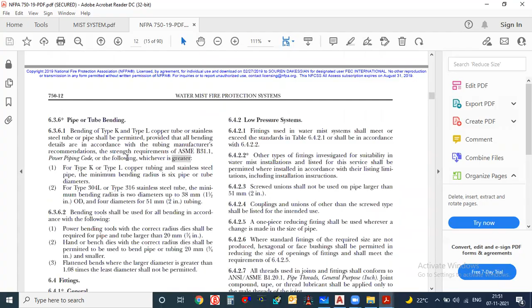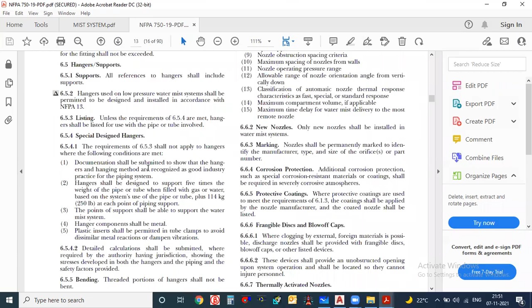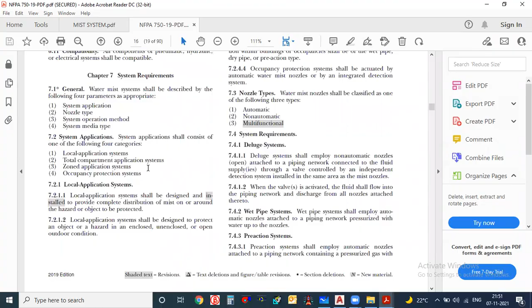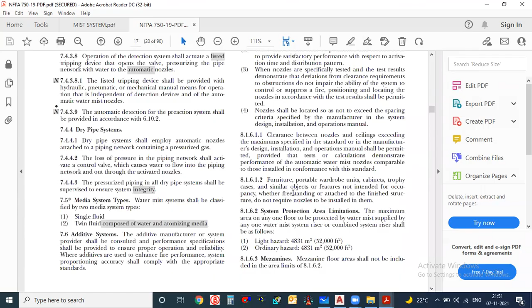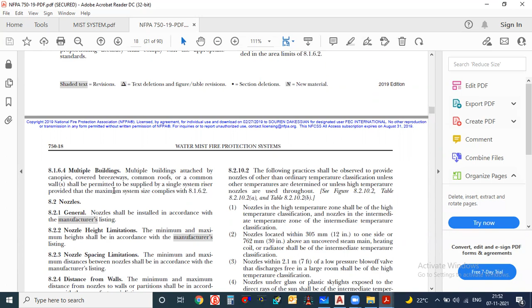And obviously, most of the details you will get from the manufacturer when you are talking about this complete mist system set. After that, what they have given, let us see. Okay, these are the system requirements they have given. After that, here they have given the protection area also, how much maximum area. So I think this is exactly similar to what is given in NFPA 13, like light hazard 4831 square meter, ordinary hazard 4831 square meter. So this is similar to what we have seen in NFPA 13. Multiple buildings attached to canopies covered shall be permitted to be supplied by a single system riser.